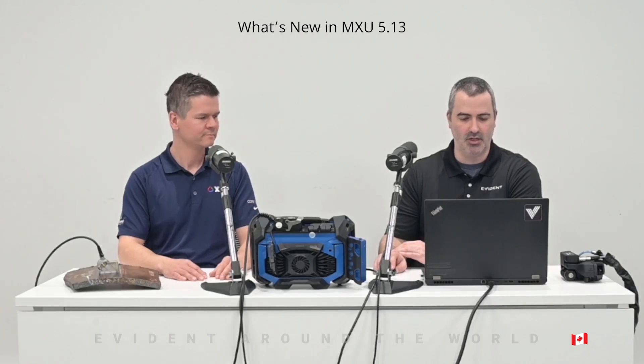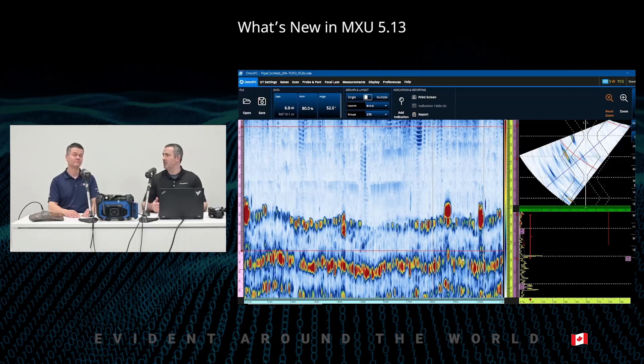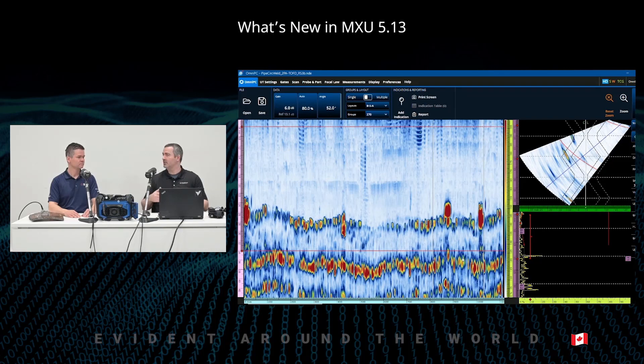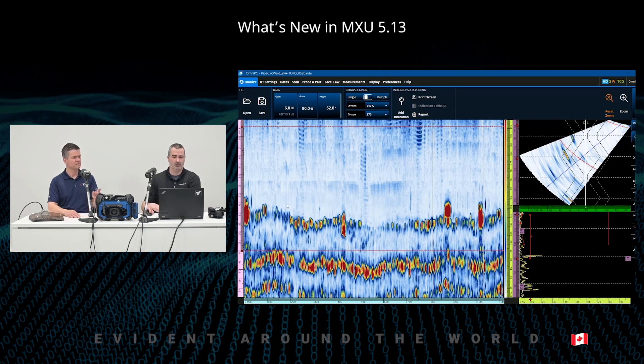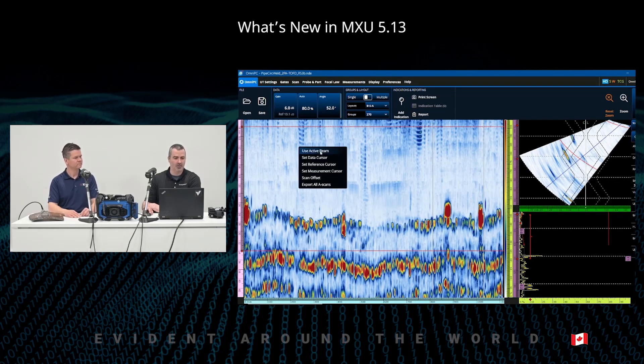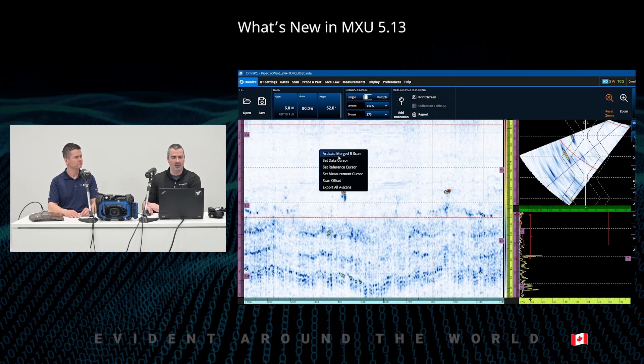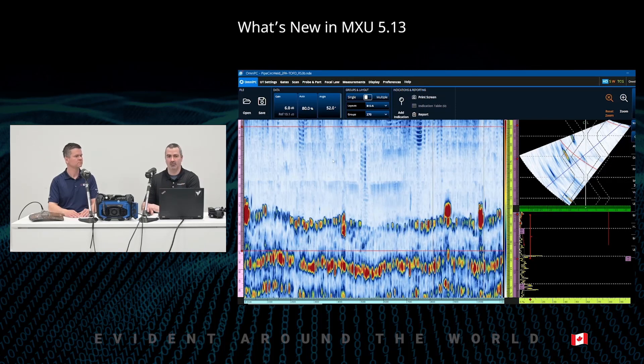The merged B-scan works on the OmniScan and on OmniPC as well. Opening the software, here's a more legitimate inspection — not just a demonstration coupon. We have plenty of root noise, cap noise, and the indications — we can kind of see them, but we have to do some work. This view has the merged B-scan active. I can turn it off and turn it back on.